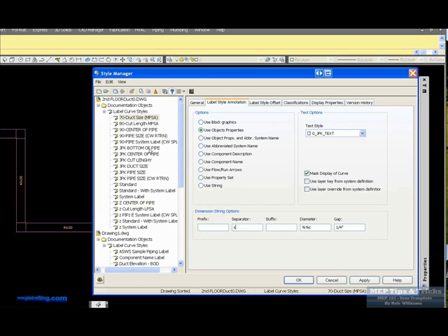I have one in here for oval. This might not be in this drawing, but I have one also for oval that has the forward slash in it. And what that's going to do is it's going to say 40/20 instead of the 40x20. And then for your round pipe, you'll have your diameter, your %C, and then your gap. Your gap will give you a quarter of an inch. It's a break line, and I'll show you that in a second. Let's change that just so I'll change it to 4 for right now. You can see the difference.